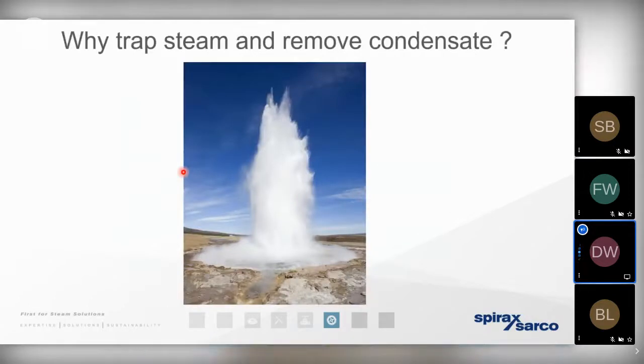So now we've understood the basics, we've had a review of the fundamentals. Hopefully we've got an appreciation for why we need to remove that condensate. The condensate is a liquid. It's got significantly less heat energy in it. So we need to get it away from the process to ensure the process can operate at an optimum rate. And we need to get it away from the distribution pipework to protect the steam system from erosion, corrosion, water hammer, to prevent the process from being contaminated with excess water, and also to ensure the energy content in the steam is as high as it possibly can be. There's no value to the process or the distribution network in leaving the condensate there. But if we can get that condensate across the trap and back to the boiler house, remember, we can use that condensate to help us to generate steam in the energy center more efficiently.